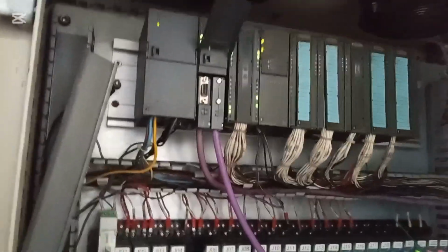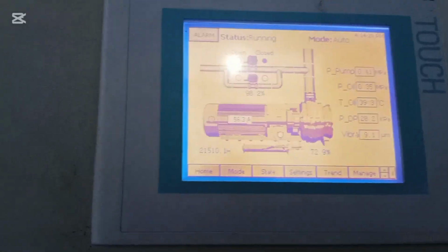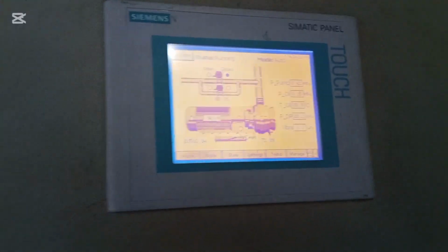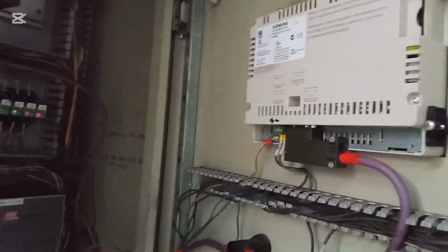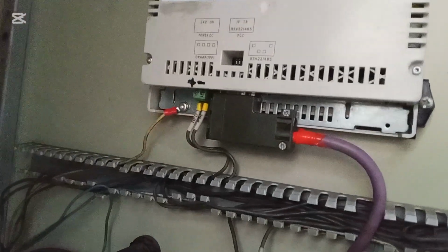After that, we again connected the cable from the PLC CPU to our HMI, and the HMI was functioning properly. In this way, we solved our HMI hang problem. For other reasons the HMI may hang, but this is one of the reasons.